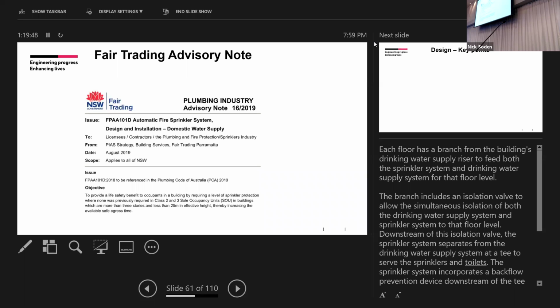One of the other advantages is that we've been putting Part 5 systems into group housing for a decade. We've had several fires in there, and the Part 5 systems have worked extremely effectively to minimise those fires. Where those fires have occurred, there's been virtually no property damage. Most of you would know that in a conventional Part 1, Part 6, Part 4 system, we're using black pipe. When one of those goes off, we end up with significant water damage, literally hundreds of thousands of dollars worth of damage.